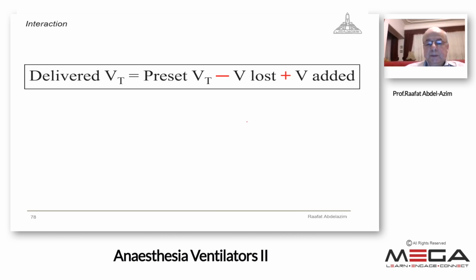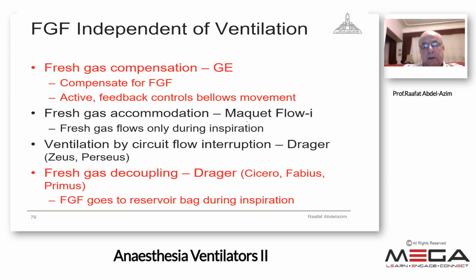Now we have newer ventilators with what is called fresh gas flow independent of ventilation. Why independent? Because the fresh gas flow will add. So to avoid addition from the fresh gas flow, we do something, according to the manufacturer of the ventilator, to stop this relationship between the fresh gas flow and the delivered tidal volume. This can be obtained according to the manufacturer.